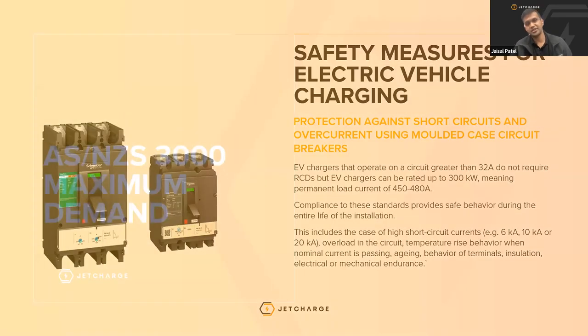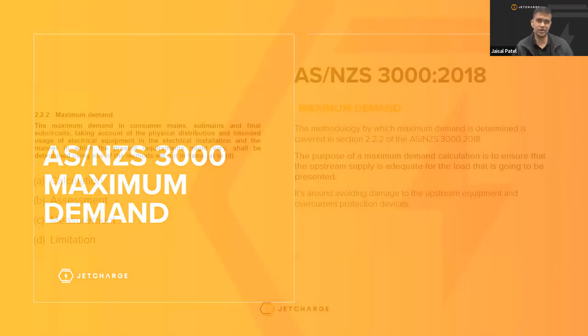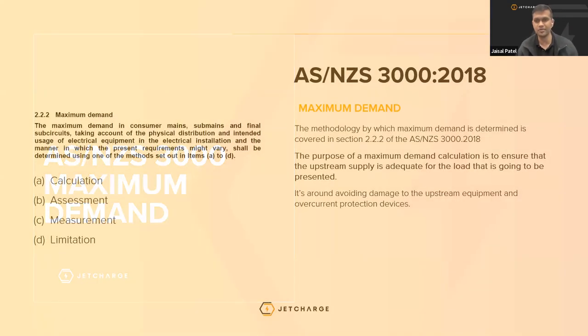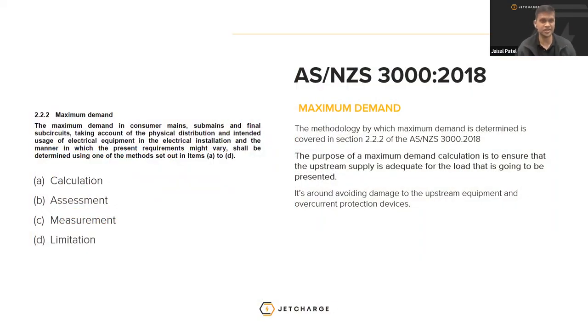Now we'll just go over AS3000, which is essentially the electrical engineer's holy Bible when it comes to calculating max demands or designing an electrical system. So the maximum demand in a consumer mains, taking into account the physical distribution and intended usage, is calculated in essentially four manners, which is calculation, assessment, measurement, and limitation.